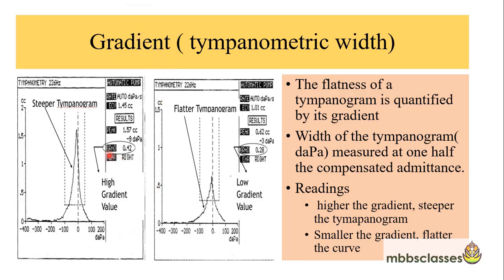The next parameter is the gradient, or tympanometric width, which describes the relationship between the height and width of the graph — essentially the flatness of the tympanogram, quantified in decapascal measured at one half the compensated admittance. Higher gradient values mean a steeper tympanogram; smaller values mean a flatter curve.